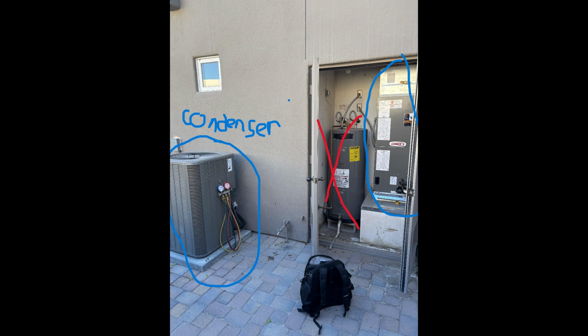which, the box on the right, if you remember, is your air handler. If it's a heat pump system, it's called an air handler. And then if you have a furnace, it's just called a furnace. And those are the two types of boxes inside. They can be in closets, they can be in your attic, they can be in your garage, and there's an evaporator coil in there. And the evaporator coil's job is to absorb heat from inside the home. And it absorbs heat by having the blower motor push hot indoor air across that coil, which ultimately leads its way out to the condenser, and then the condenser's job is to reject heat.